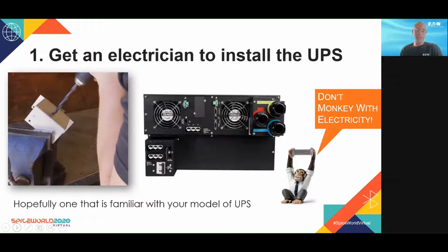But yeah, so Mike mentioned we're going to talk about some tips. Let's jump right into 10 useful tips when buying and installing your backup power equipment. Tip number one: have an electrician install all hardwired UPS units, with a big emphasis on hardwired. An exception can be made for plug and play models, usually seen at or under 5 to 6 kVA. You're generally good to go, but it still isn't a bad idea to have someone review your work afterwards. This is especially true with many of our 9PX, 9SX, and 5 series models.